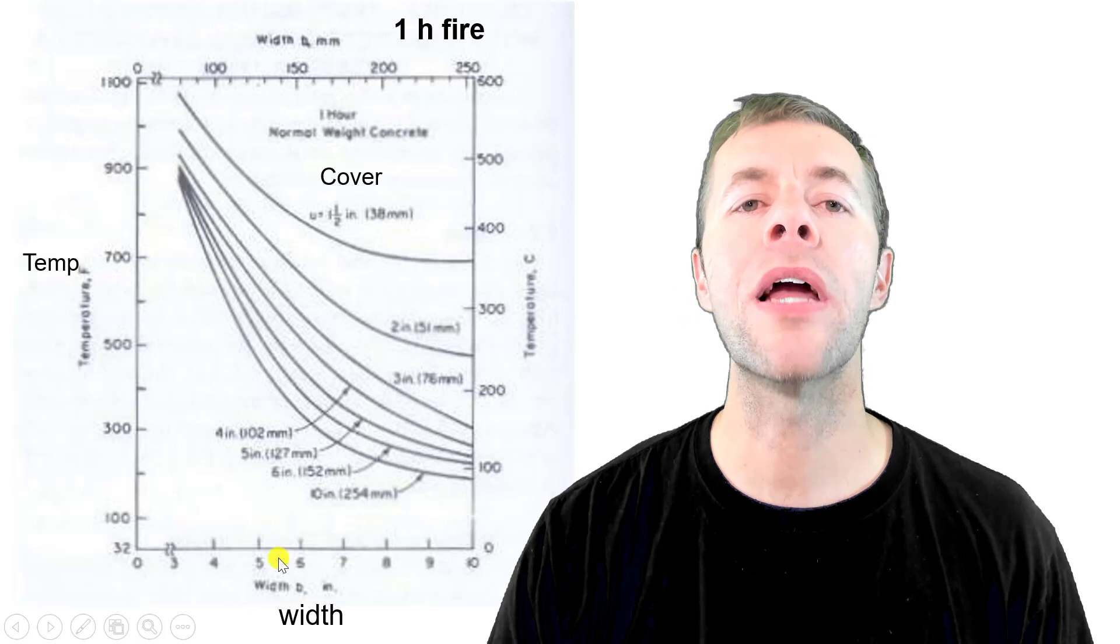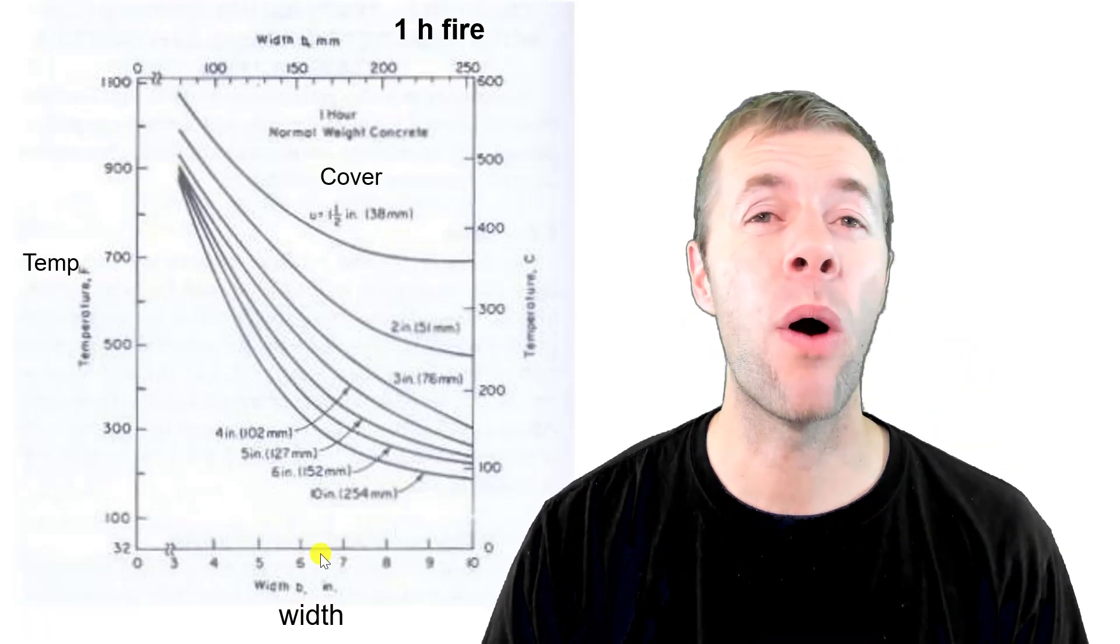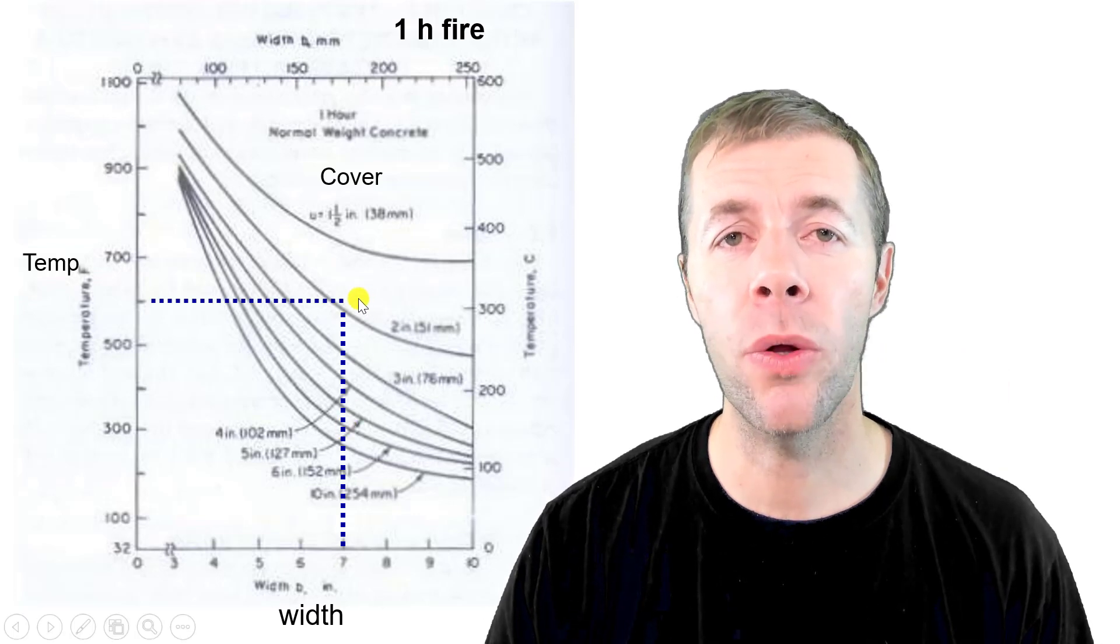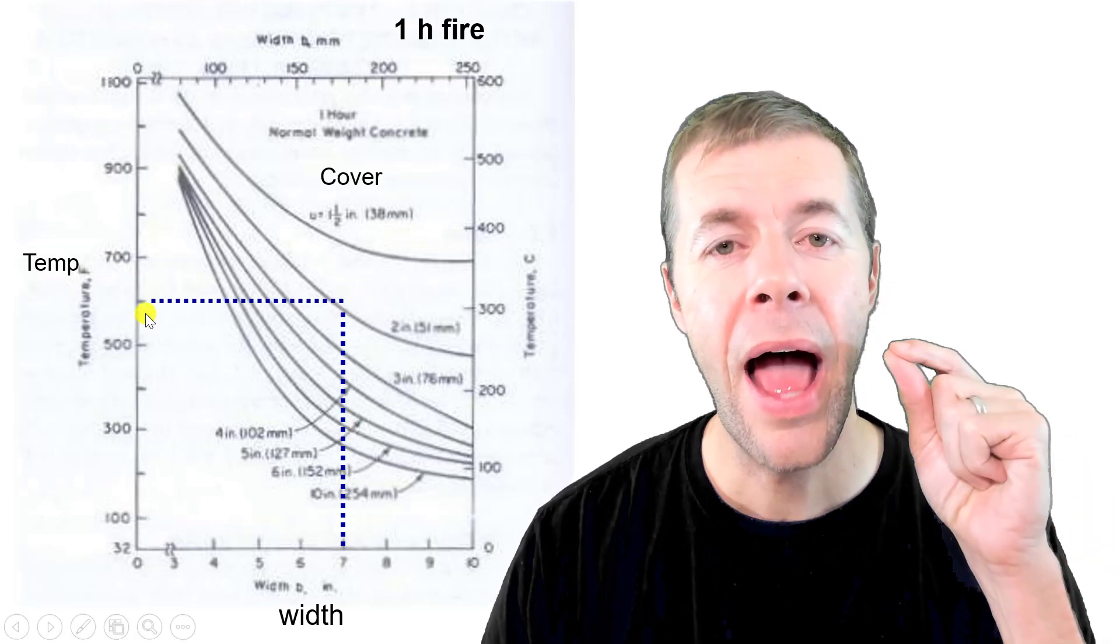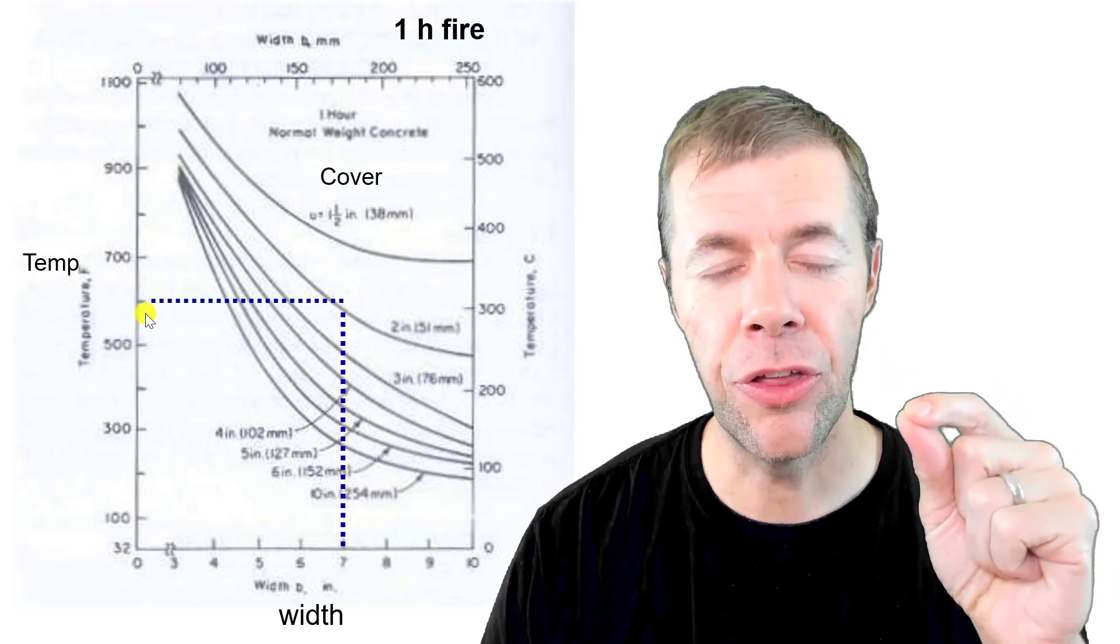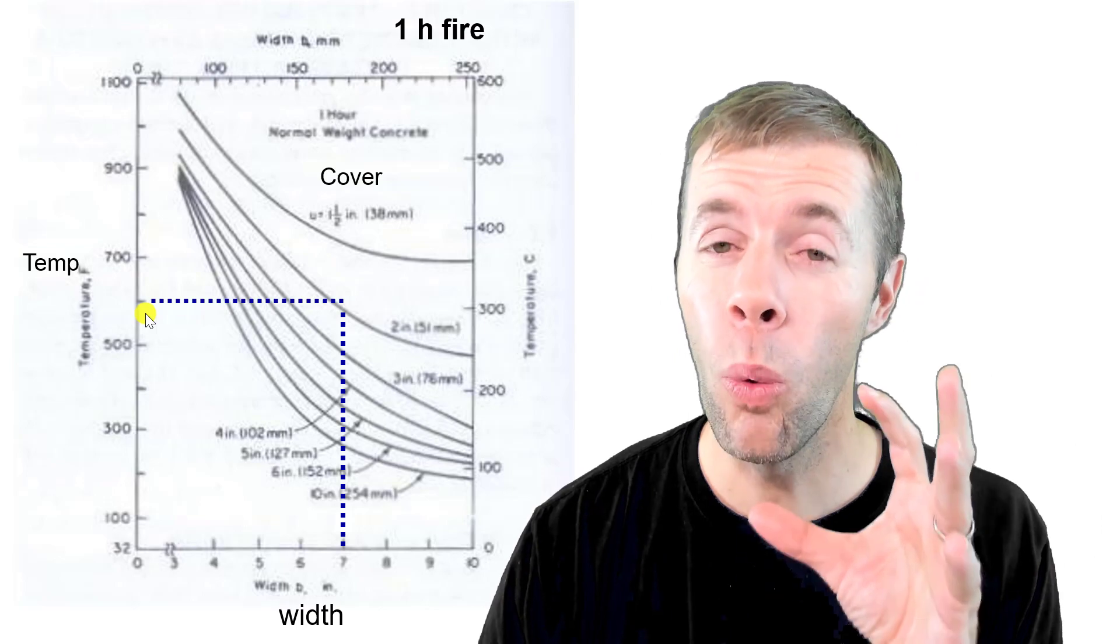Here's another one where I come in with the width of my beam. This is for a one hour fire and I go up until I hit a cover, and that will tell me the temperature at that depth inside the concrete. Now that's an estimate for a typical one hour fire.